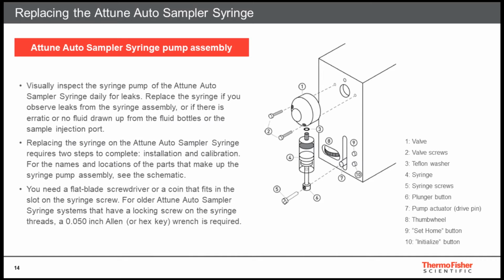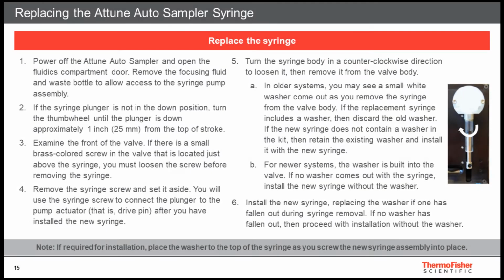Replacing the Attune Autosampler syringe, although slightly complicated, is like changing any other syringe. This procedure in the next few slides refers to the Attune Autosampler and not the CytKick Autosampler. A flat blade screwdriver and 0.05-inch Allen or hex key are required for this procedure. Start by powering off the Autosampler. Open the fluidic compartment door. Remove the focusing fluid container and the waste container in order to gain access to the syringe.